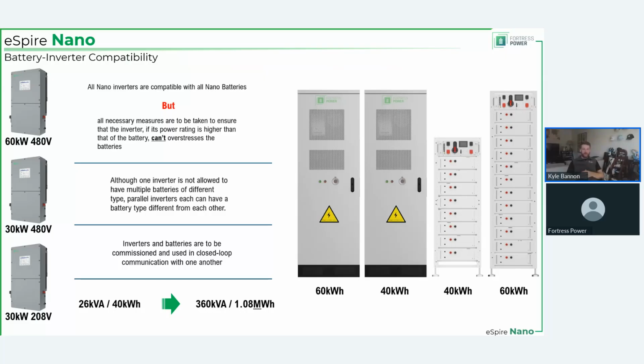So that is the range you see at the bottom there. That's the smallest project you could conceivably do with an eSpire Nano, at 26 kVA, 40 kilowatt hour at 208 volt, all the way up to 360 kVA—that's six of those 60 kW inverters, each paired with three of these 60 kilowatt hour battery cabinets, for a total of over a megawatt hour of energy storage.